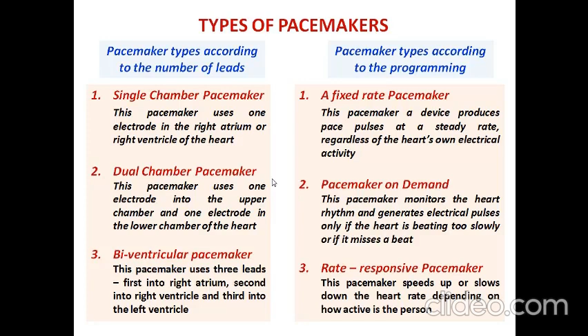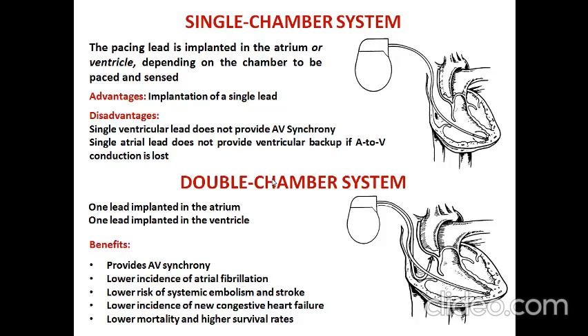Now let us see the importance of single chamber and double chamber systems. In a single chamber system, the pacing lead is implanted in the atrium or a ventricle, depending on the chamber to be paced and sensed. In the case of a double chamber system, one lead is implanted in the atrium and one in the ventricle. Both have advantages and drawbacks, as already shown here. Compared with the single chamber system, the double chamber system has very good benefits, and we mostly use the double chamber or biventricular system for practical applications.